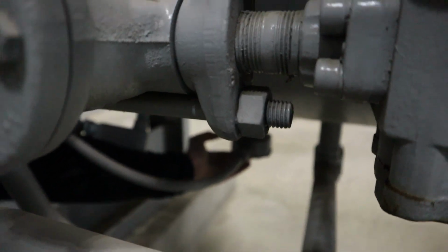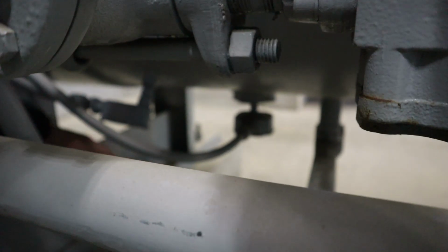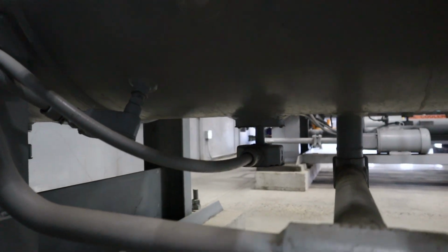This prevents ammonia vapor from condensing in the crankcase or oil separator and ensures the oil will flow when the unit starts. Oil heaters are typically controlled by a thermostat to shut off at approximately 100 degrees Fahrenheit. It is unnecessary for the oil heater to be on when the compressor is running because the heat of the compressor is sufficient to maintain good flow characteristics in the oil.